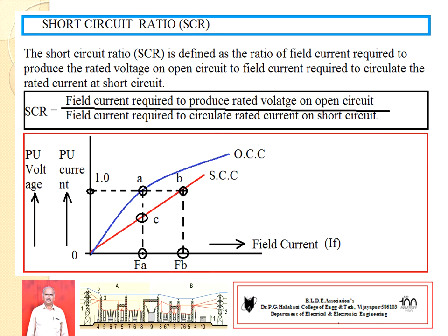SCR is defined as the ratio of field current required to produce the rated voltage on open circuit, to the field current required to circulate rated current at short circuit. You already know how to plot the OCC (open circuit characteristics) and SCC (short circuit characteristics) by varying the synchronous generator excitation, i.e., by varying the field current.